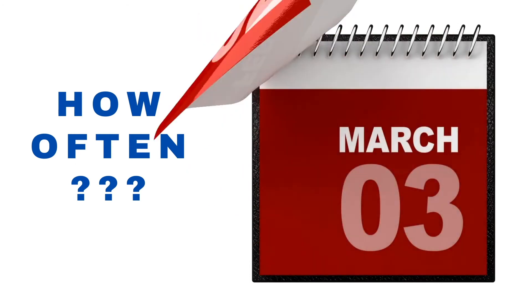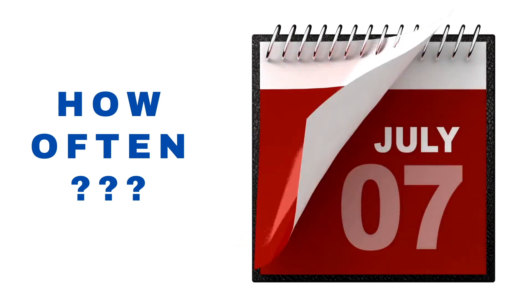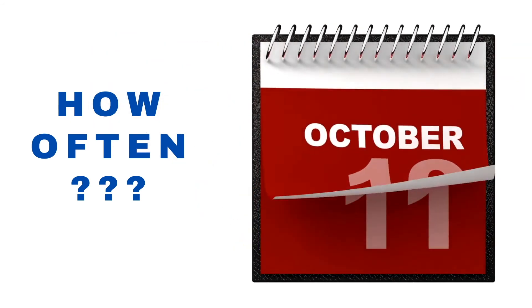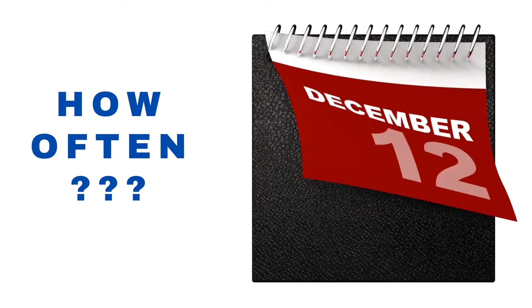The question may come up: how often do I do an inspection? Ultimately it's up to your healthcare organization, and that'll depend on state and national certifications they're trying to maintain. They're going to look at things such as manufacturing guidelines, historical data, and the risk of the equipment. Typically, higher risk devices are going to be inspected more often and lower risk devices less frequently.